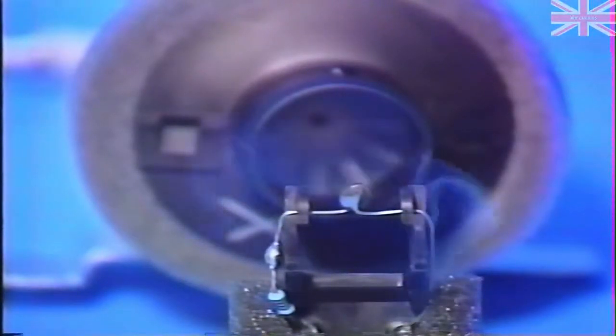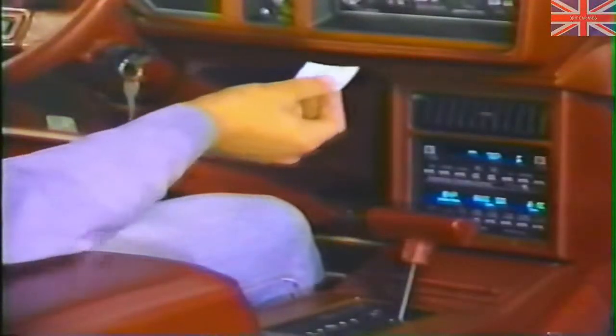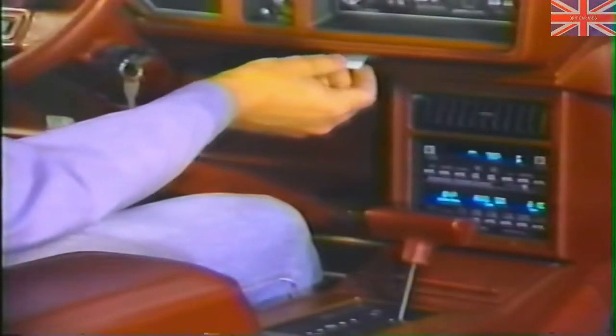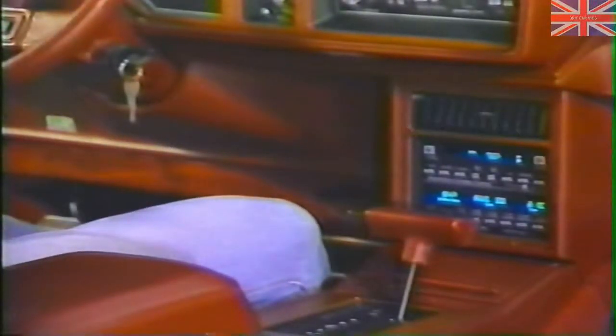In some instances, a small blower motor is used to draw air through the aspirator and across the temperature sensor. In others, a vacuum or Venturi principle is used in the aspirator or ductwork, again supplying a continuous flow of inside air across the temperature sensor.